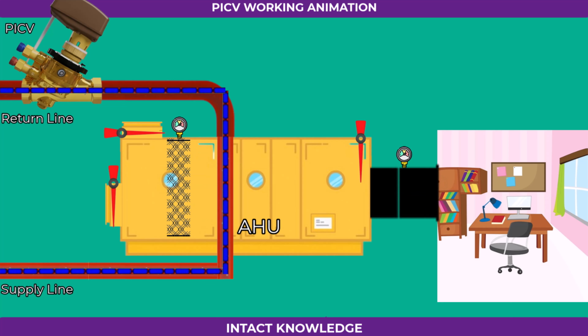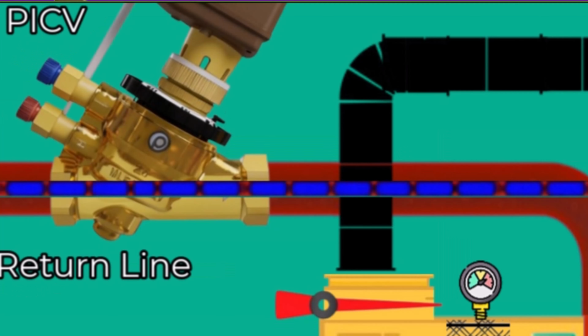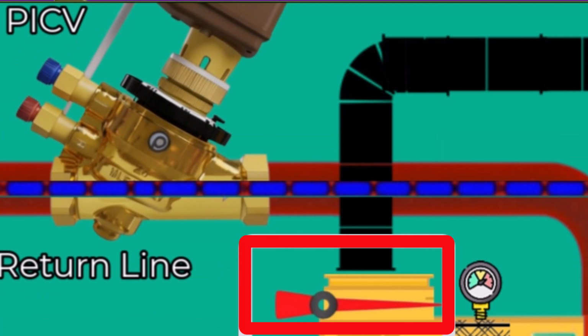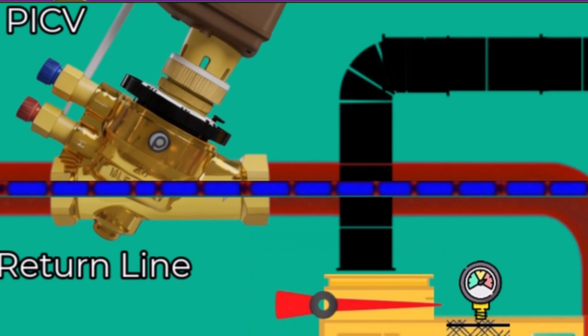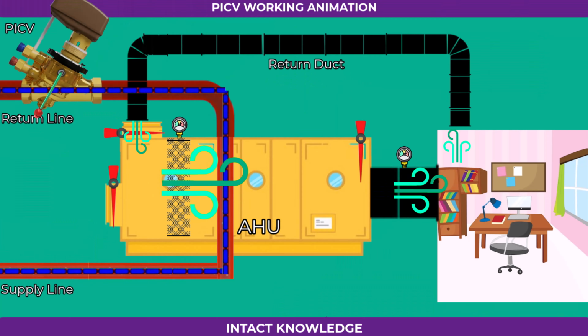Now, once the room reaches the desired temperature, cooling is no longer required. At that point, when air returns to the AHU through the return duct, a temperature sensor inside the AHU detects the temperature of that returning air. When it finds that the temperature has reached the set point, it sends a signal to the actuator mounted on the PICV. The actuator then moves the stem downward, closing the valve and stopping the chilled water flow. This action stops cold water from entering the coil, preventing further cooling of the air. As a result, the system maintains a stable and comfortable temperature in the room.